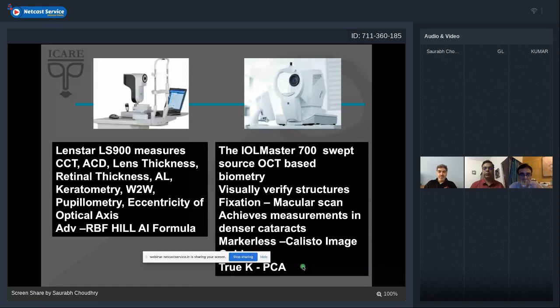Meanwhile, the IOL Master 700 is based on the swept source OCT technology. You can actually visually verify the structures, and the fixation is the most important bit of it, because the macular scan of the OCT can actually tell you that you fixated right in the center. And now it gives you the true K values. That means the posterior corneal astigmatism can be calculated on this machine as well.